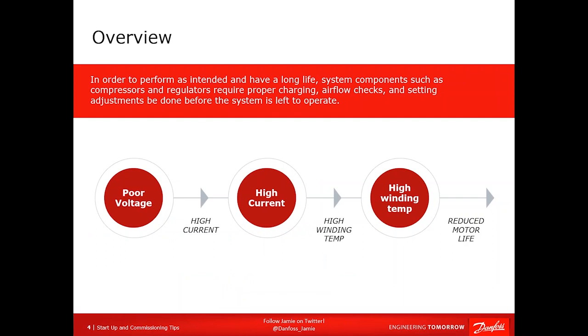Have you ever heard of situations where a compressor has run for 25 or 30 years? It's a given that this compressor operated in ideal conditions. Ideal, not in a fairy tale sense, but it had good voltage, good airflow, it was clean. All these things happened so that it could continue to run. That is often more important than how well the compressor was manufactured. As long as it has everything it needs, most of these compressors and other parts of the system should run for 15 or 20 years.